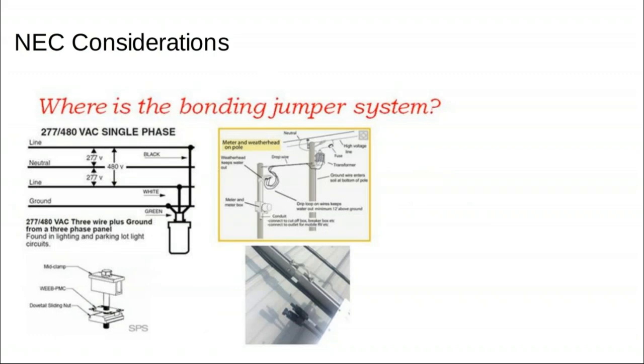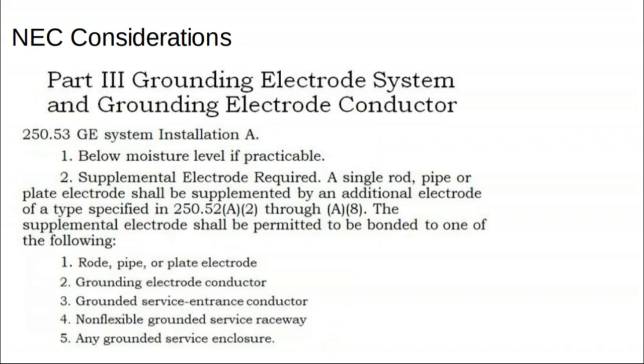What I'm trying to say here is, the utility is grounded out at their transformer, and then the home has its own grounding electrode. You might be surprised that your grounding electrode system needs your grounding electrode plus a supplemental electrode.